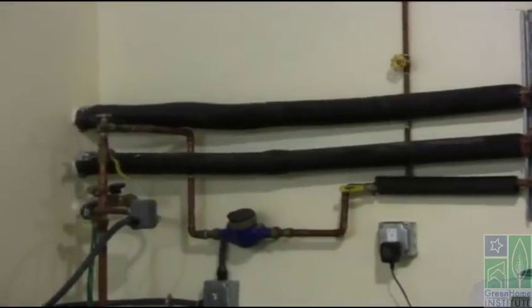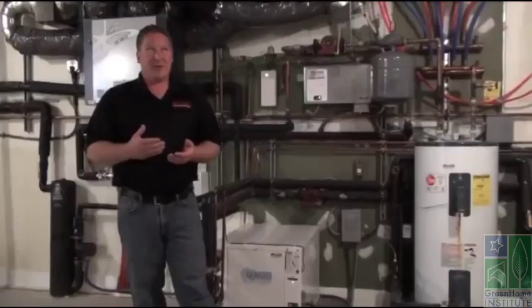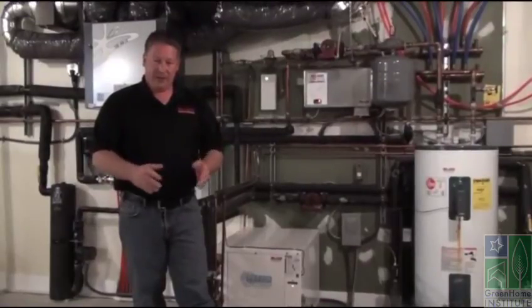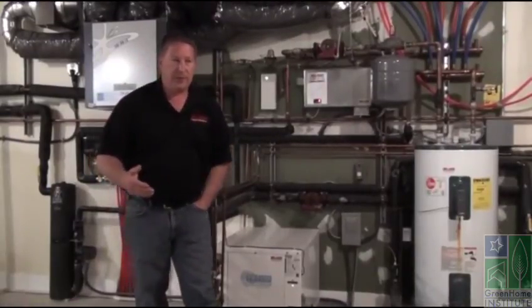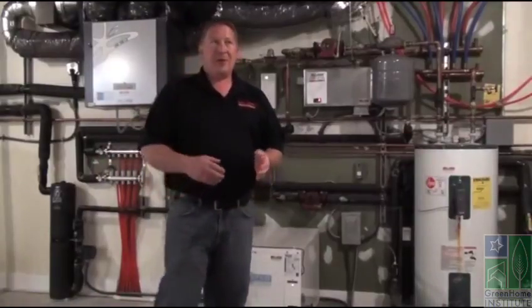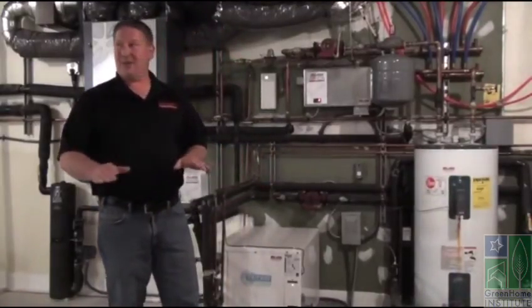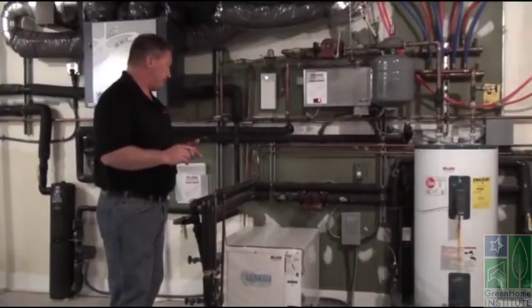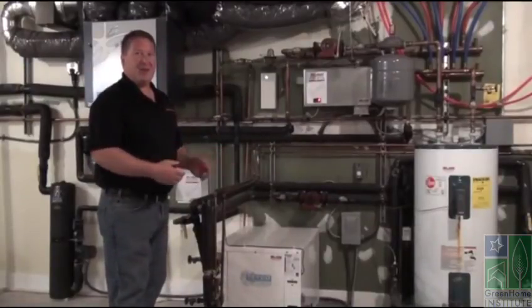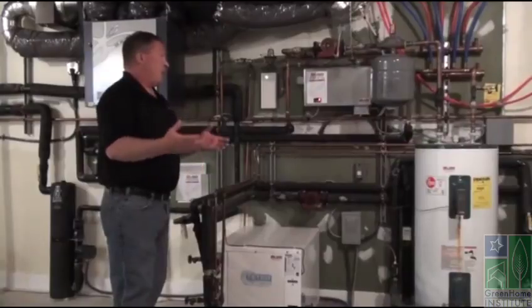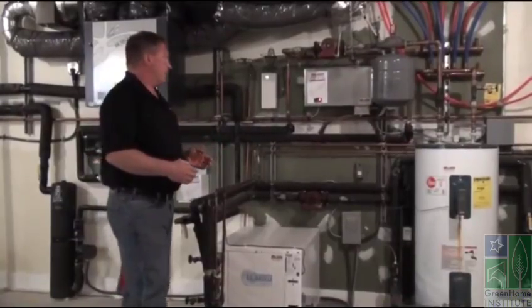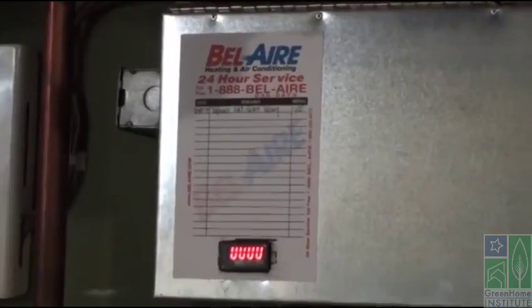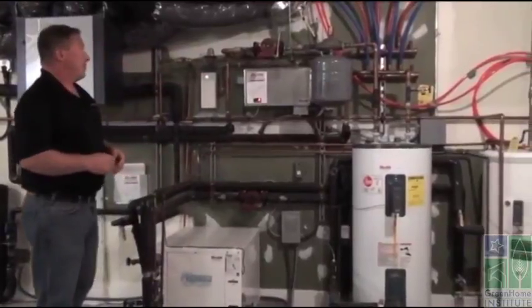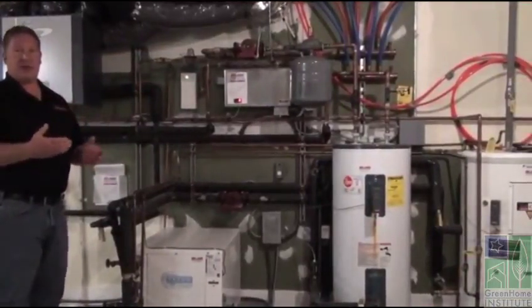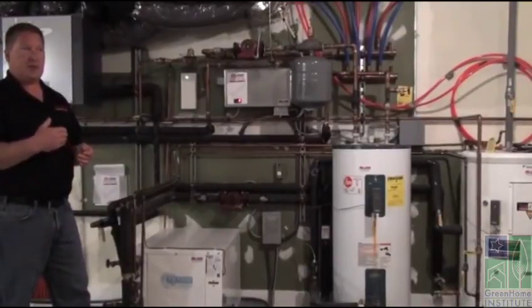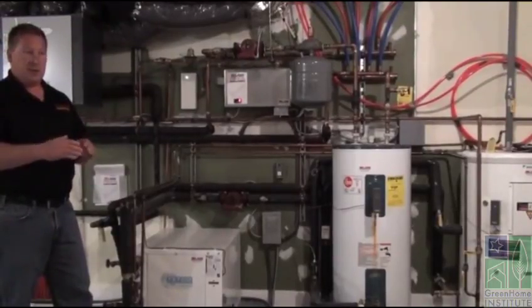In the summertime, there's a lot of moisture in the air. And if there's a lot of moisture in the air and we're cooling off a floor, getting a concrete slab cold, we could end up with condensation on the floor. Water in houses is not a good thing. It causes mold, and the unit just satisfies its demand. But water in a house is not a good thing, so we have a control system that you can see that actually monitors the dew point upstairs in the space to make sure that we don't get near that dew point and start to condense water in the house.